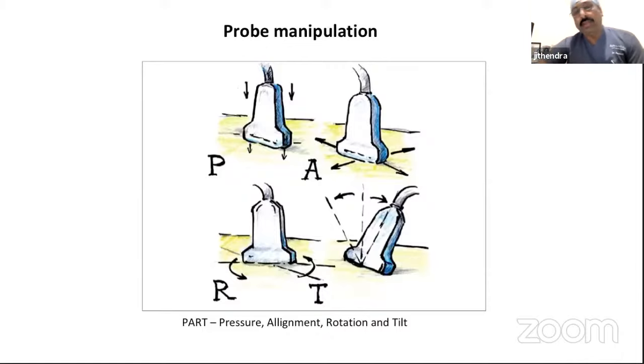Suppose the target which you need to see is at a depth of around 6 centimeter, with a little bit of 2 to 3 centimeter thickness of fat. You can actually use a little pressure with the probe on the skin, and then the depth is reduced, and the structure which needs to be targeted comes a little higher up and comes into the view between 0 to 4 centimeter, and you get a better image quality.